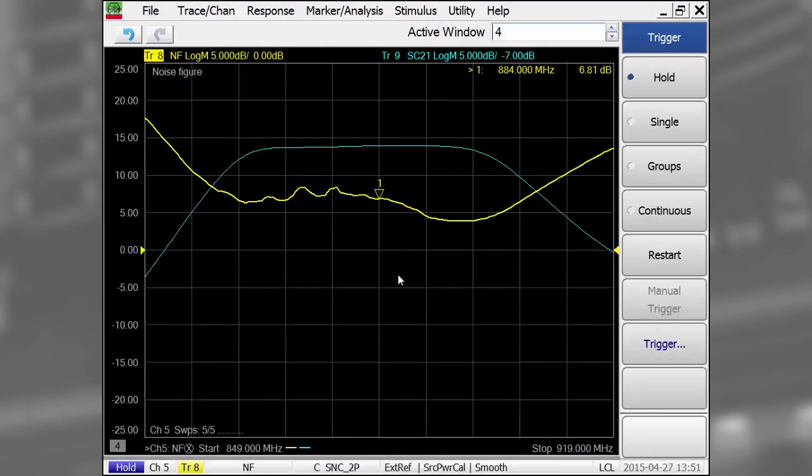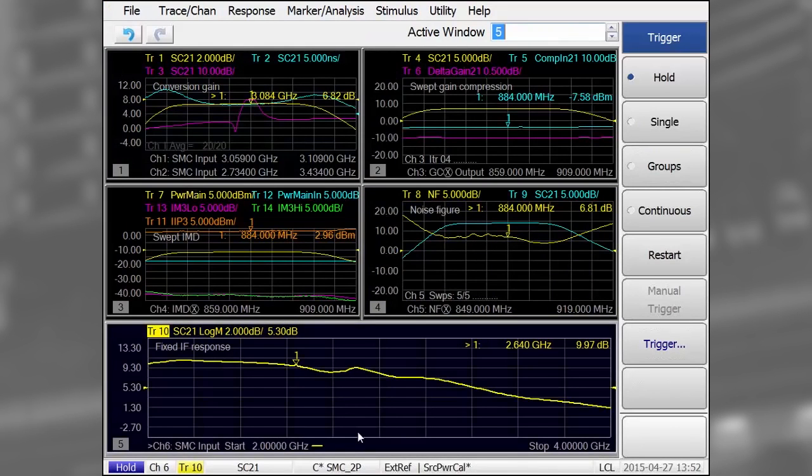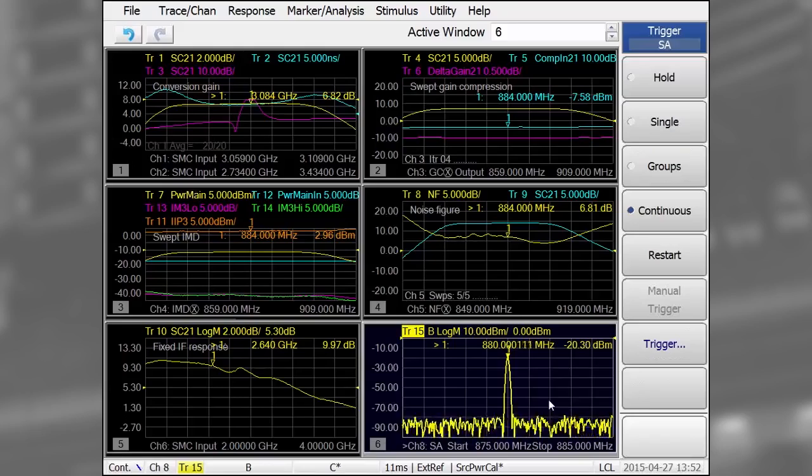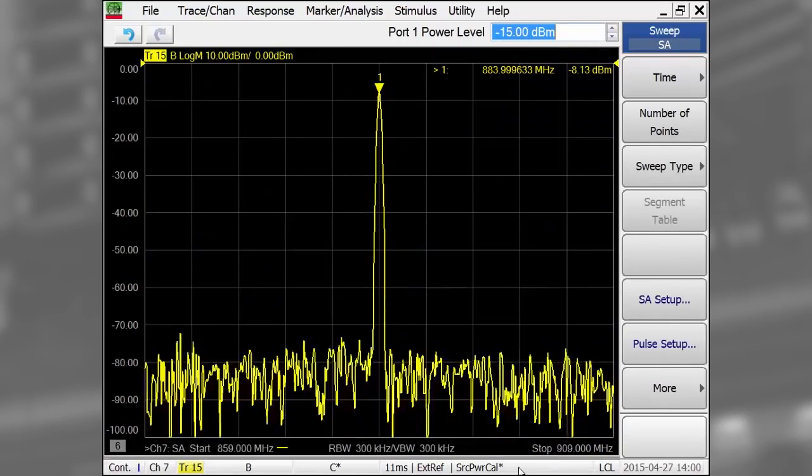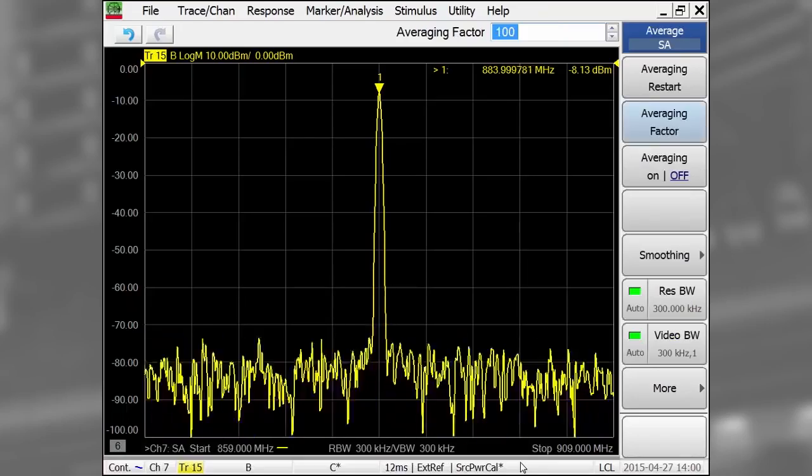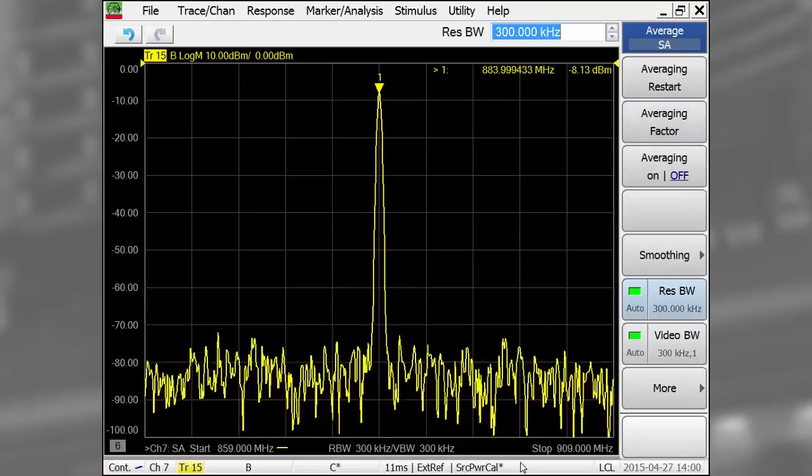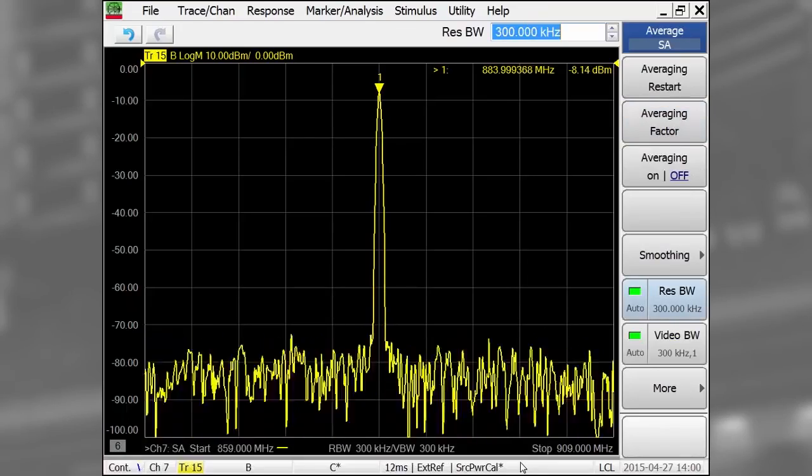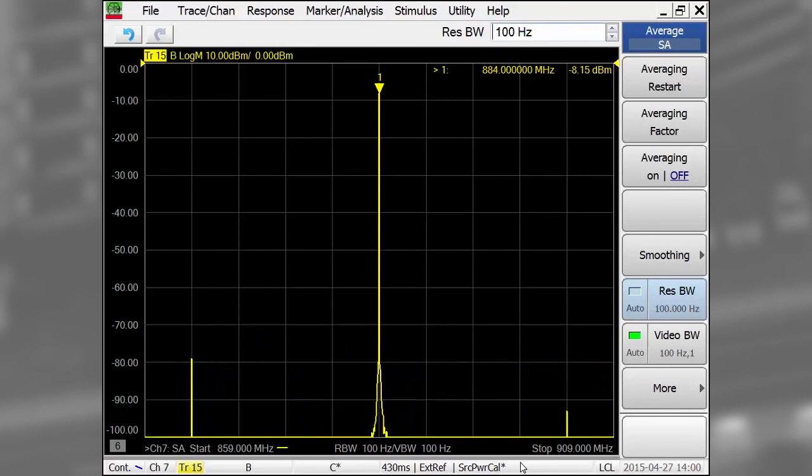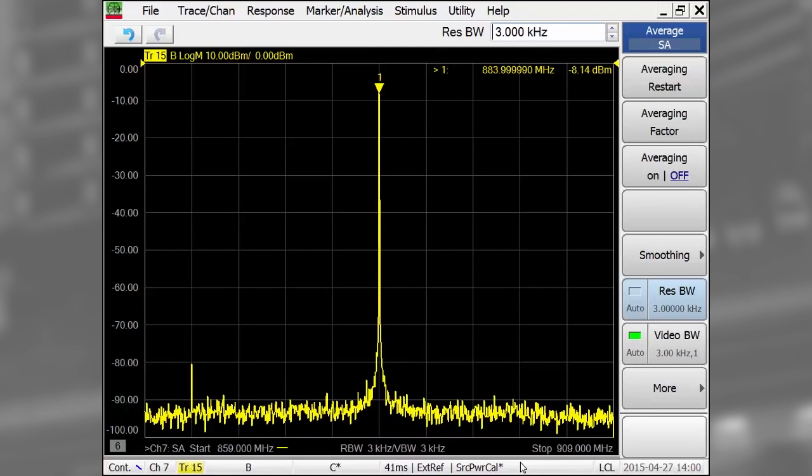Taking advantage of a feature called marker-to-SA, I can place a marker in the pass band of the converter and open a spectrum analyzer channel that has the same stimulus conditions as those used in the noise figure channel. Now we see the output signal at 880 MHz with a 50 MHz span. Notice as I decrease the resolution bandwidth setting, I can maintain excellent sweep speed while improving measurement sensitivity.